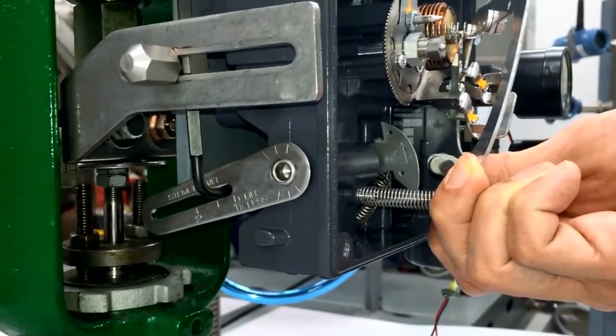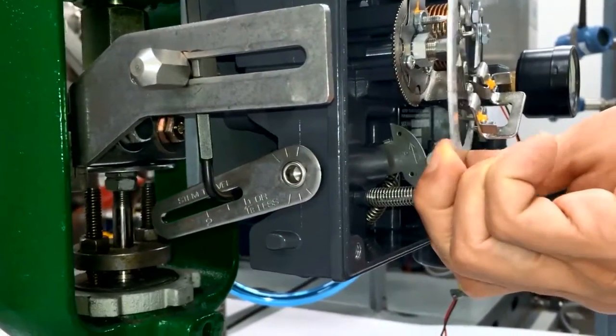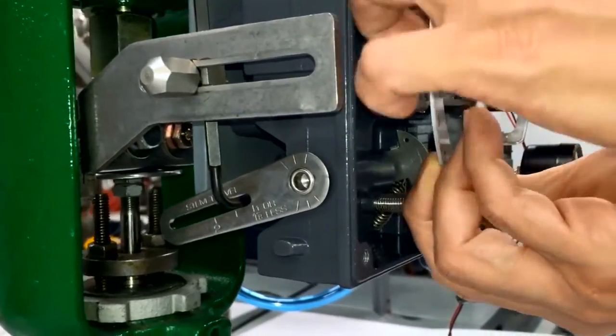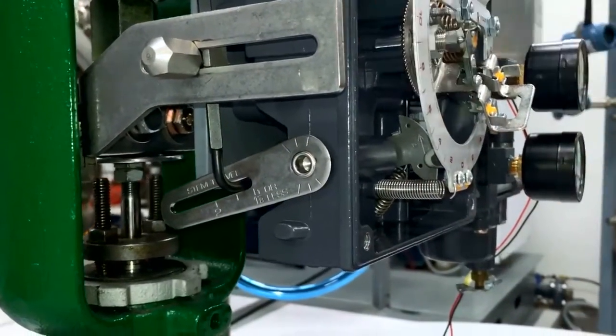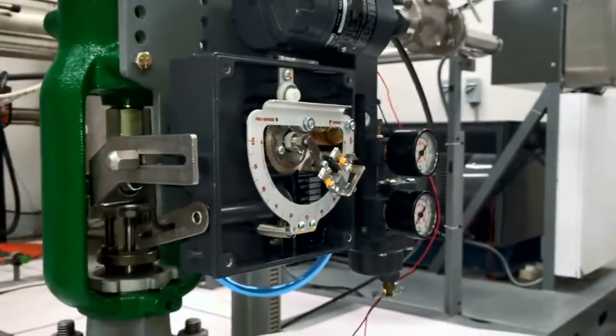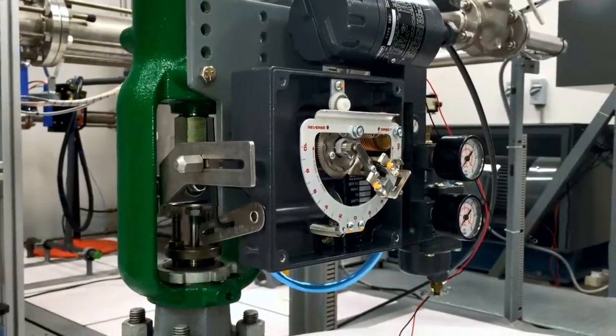In our case, the arrow on the cam should be pointed up. This means that when you put air into the actuator the stem moves up, which is correct in our setup. For details on how to change the cam arrangement, please refer to the instruction manual.